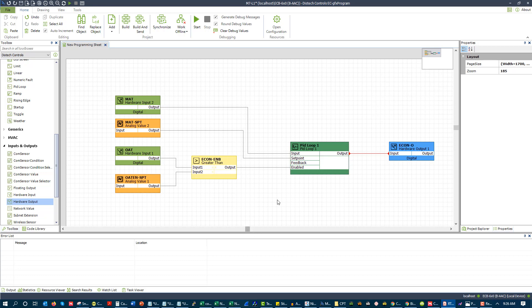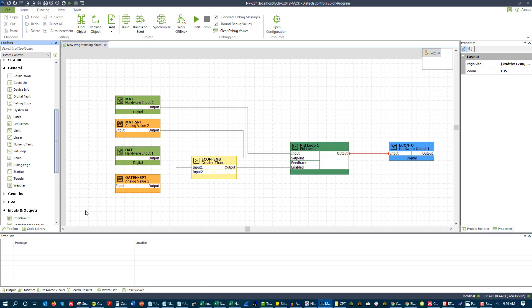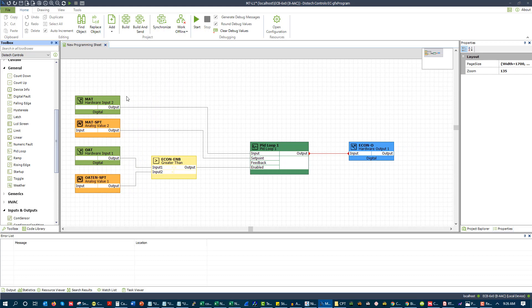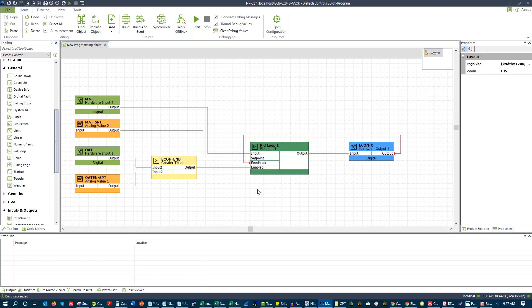So really the true gist of all of this is threefold: understanding your logic blocks, understanding how sequences work, and understanding the software. The OEM training will teach you the software. We have training that will teach you how logic blocks work and all of these design patterns, and training that will teach you the HVAC sequencing as well. But you see this pattern right here: mixed air temp, mixed air set point, PID loop. So input, set point, enable point, economizer output — our output being driven off of our PID loop. And with this particular software, we can provide feedback. This is a design pattern and you can start to see how these patterns come into play.